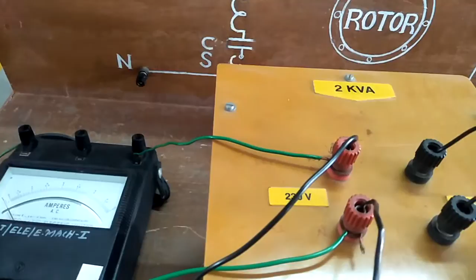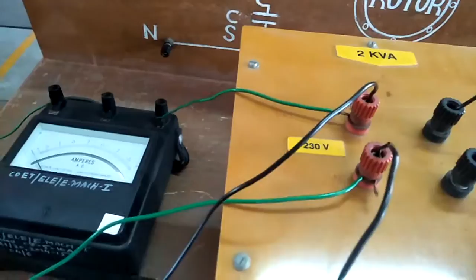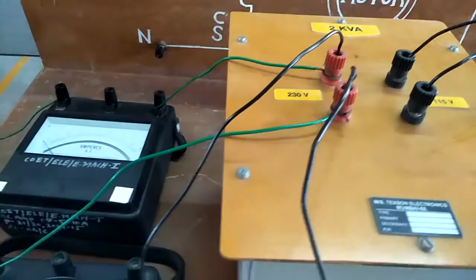Now what we will do is measure the voltage ratio. What would be the voltage ratio? If this is 230 volt and this is 115 volt, the secondary winding is half of the primary, so the ratio is 2:1. So when we apply 100 volt, the secondary voltage should be around 50 volt, and so on.